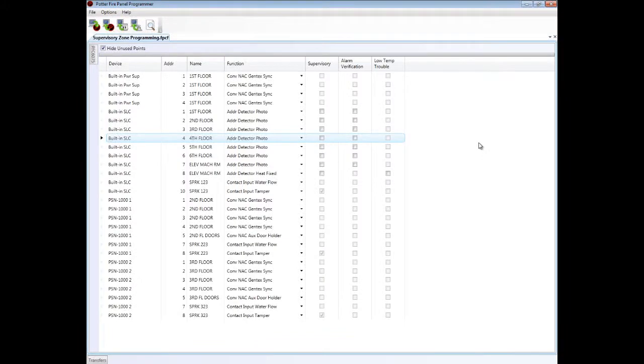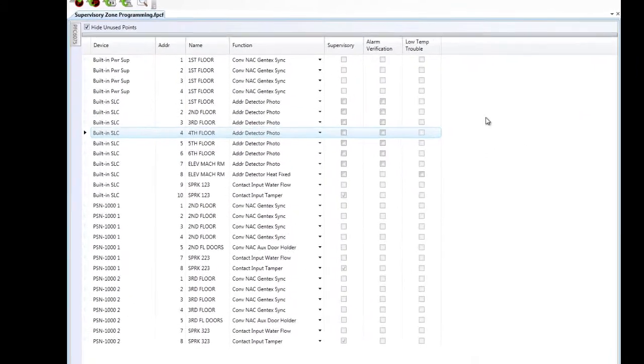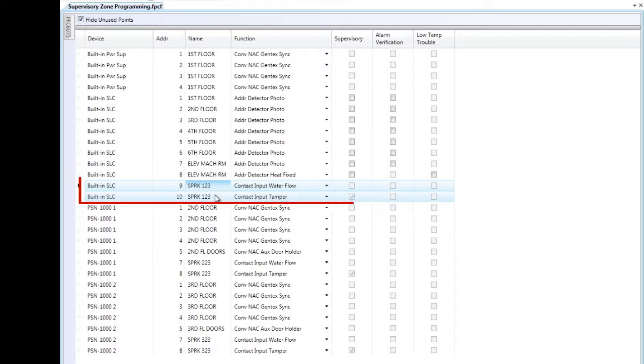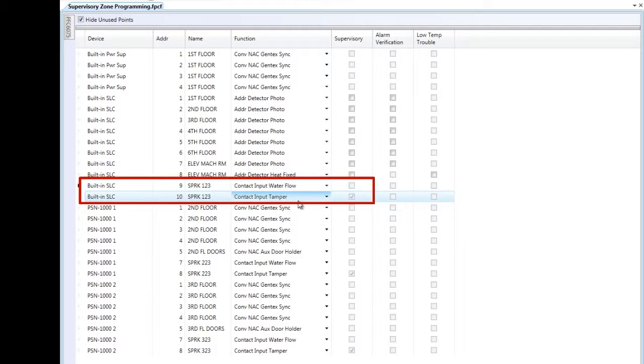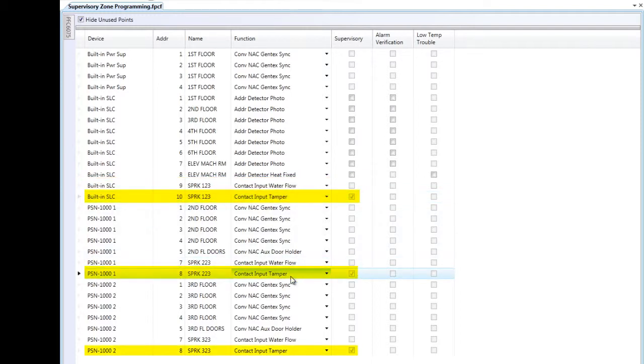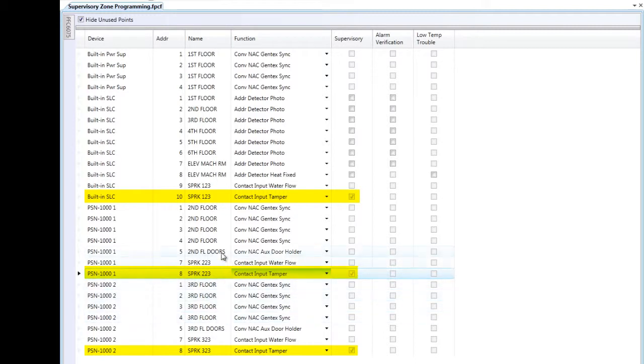What you're looking at here is the points list for a PFC 6075 that I have started to customize. I have a DCM module located at address 9 and 10, and I've created one point as a water flow and one point as a tamper. It has automatically assigned that tamper as a supervisory condition, and I cannot change that. I also have a tamper condition located on my PSN 1000 on both the second floor and the third floor, as you can see here.